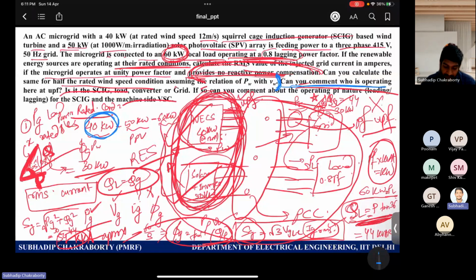Because this line created the whole problem: it provides no reactive power compensation. So it's saying that the microgrid as a system, as an AC system, is not providing any reactive power compensation to the load, because the load needs some reactive power. But the microgrid as a system will not push or provide any reactive power compensation, so the grid will compensate. So then who is operating at unity power factor? Because neither the load nor the grid is at unity power factor.